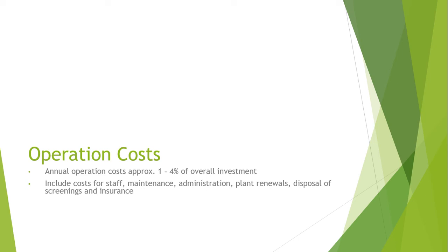The annual operation costs are approximated to be around 1 to 4 percent of the overall investment. For small and very small hydroelectric power stations they are generally higher than for the larger plants.